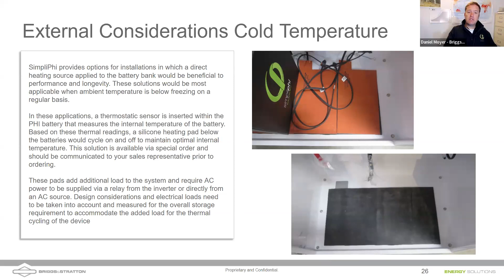There are, of course, other devices. Victron makes one, for example, that has its own temperature sensor. So you can take that thermistor that you see on the far right there and perhaps sandwich it between two batteries. So although we're not having a thermistor embedded inside the battery, sandwiching them between two batteries is going to get us a little bit closer to reading internal battery temperature and not ambient temperatures. And then based on the signals being sent from that thermistor, this charge controller from Victron can adjust its charge rate so that it's not charging the battery too quickly at a cold rate.